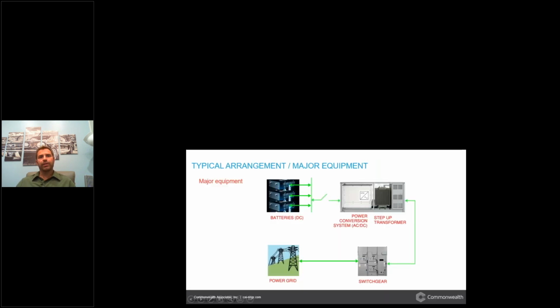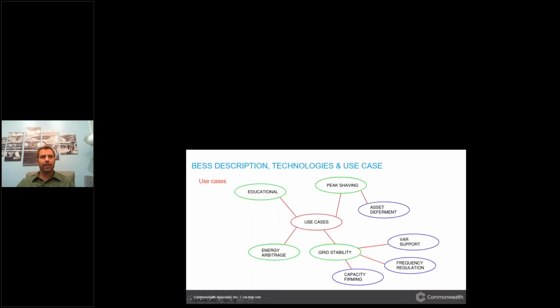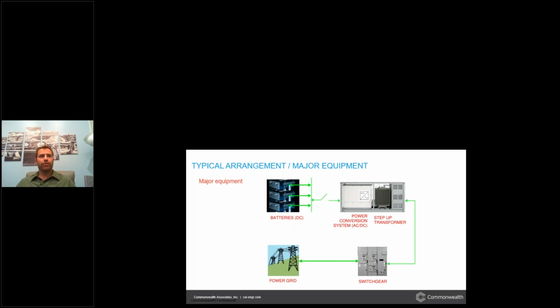power conversion system, or PCS, is an inverter and converter. Because this process is a two-way street, the power conversion system has to do both. Charging and discharging, it's converting and inverting. Unlike solar, where power does not have to flow in two directions, only an inverter is needed to make the system work. From the PCS, the AC voltage is stepped up to whatever the distribution voltage is in the area. Commonly we see 12 to 35 kV, but I've definitely been involved in projects where we're connecting up to 345 kV. Then the step-up transformer is connected to switchgear. Switchgear is where a lot of protection and controls are enclosed. Breakers with sophisticated relays protect the BESS system from itself and the grid. And then from the switchgear, power flows to and from the grid.